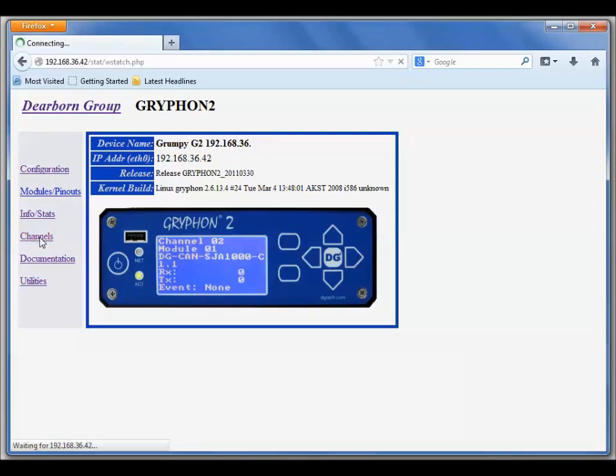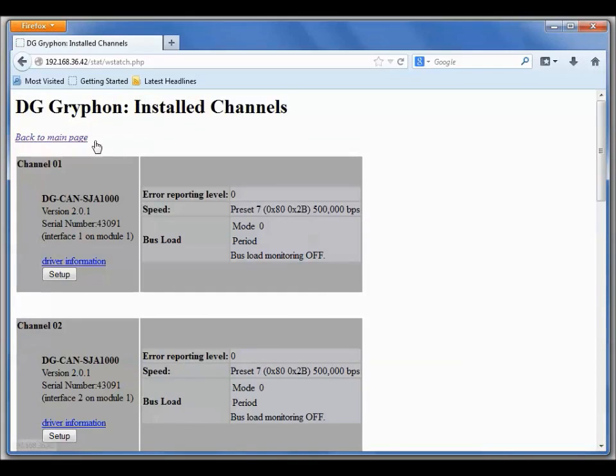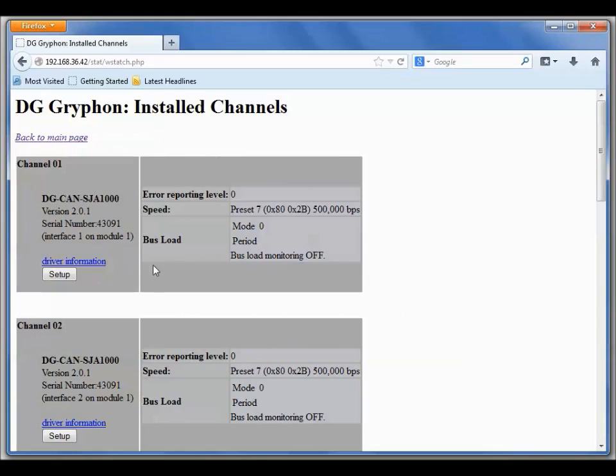If you click on channels here in the web interface, it will take you to the web page that shows you the details for the installed channels. Here we can see the first two channels are CAN-SJA1000, and over here is the baud rate. The first channel is set up for 500k and the second one is set up for 500k also. That's exactly what I want.